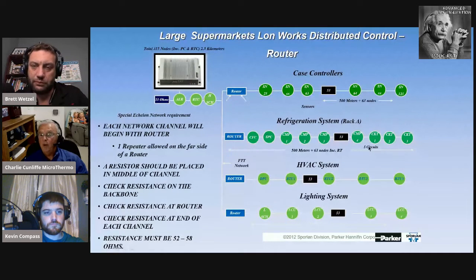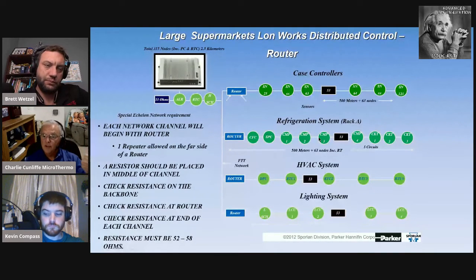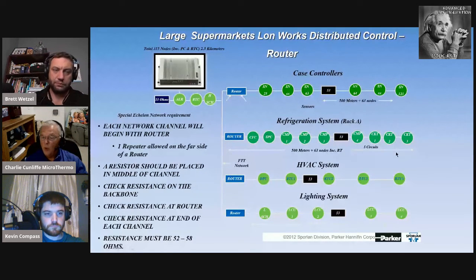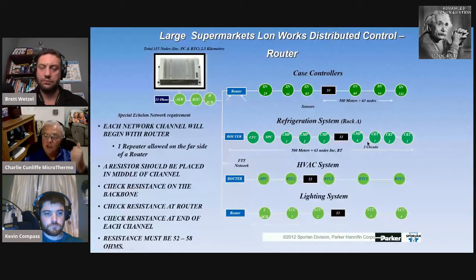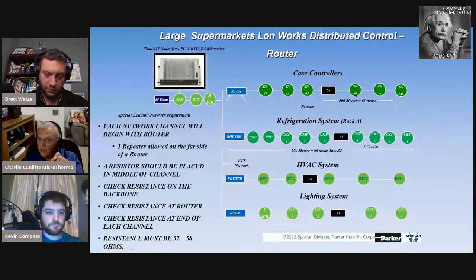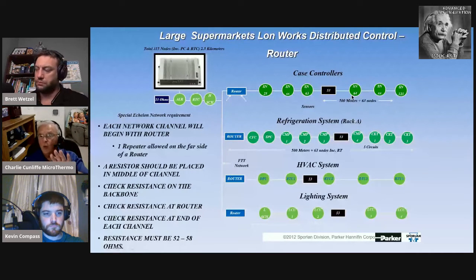An example would be doing HVAC in the store. I've hung a temperature sensor and a relative humidity sensor so the HVAC system works better. The beauty of a network is that's an Echelon device, and it puts the temperature and humidity on the network. So all I have to do is tell each case controller, by checking a box, to listen to that parameter, which is always automatically broadcast on the network.